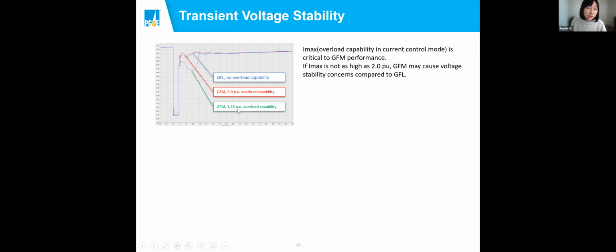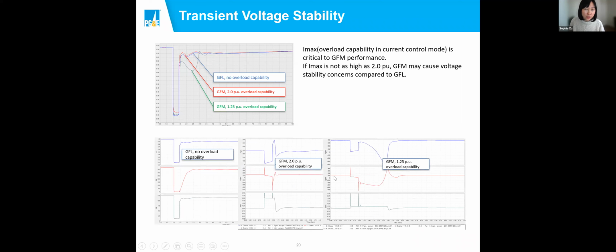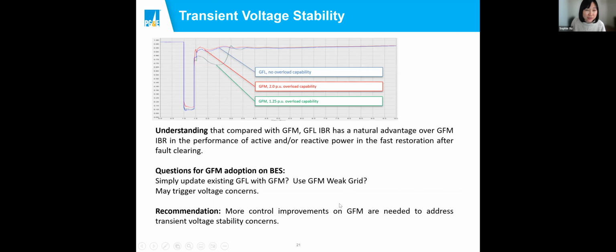Still kind of 25% overload capability more than the grid following, because grid following here doesn't have the overload capability that I have in my model. And then you can see a pretty significant voltage dip post-contingency. I think it's majorly because of the faster recovery in real power and the reduced Q post-contingency causing this. I don't have much time left, so I will leave the detailed plots comparison to questions.